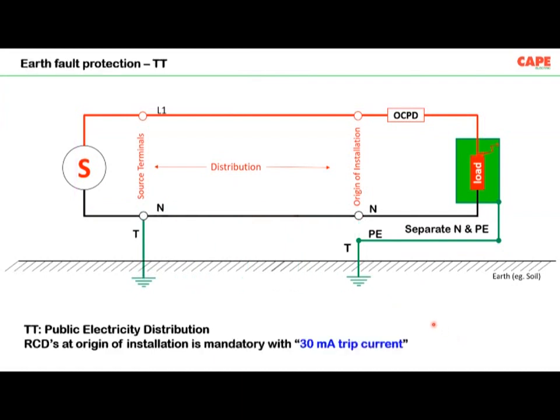In the case of the next network, which is called a TT network, the source is earthed to an earth electrode in soil. The equipment side is connected to a different earth electrode in soil. Imagine there is a fault. The fault current returns to the source through the earth electrode, through the soil. It returns back through the system, the power supply earthing. So through the equipment earthing, it goes to the earth electrode, and through the system earthing, it comes back to the source. And finally, the fault loop circuit is closed. Now, under this condition, the resistances of the earth electrode at the source side and at the equipment side come into the picture. As a result, the fault current will be very much less. The fault current is not enough to trip an MCB. So the very simple solution provided in the standard is to put a 30 milliampere RCD at the origin of the installation.